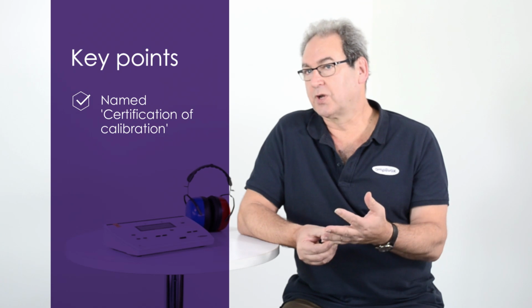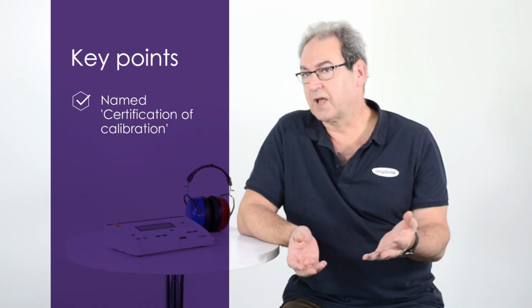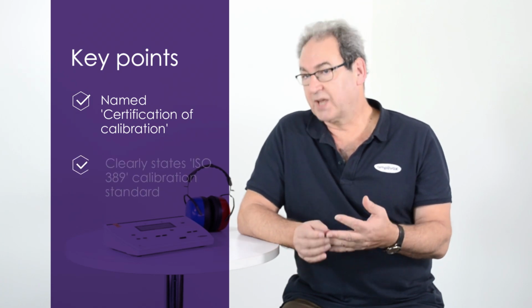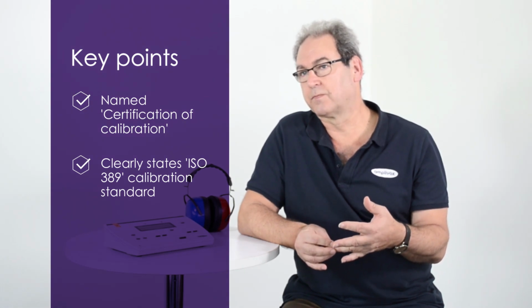So once the calibration has been completed, a calibration certificate or certificate of calibration will actually be issued for that specific audiometer and headset. The key point on a calibration certificate is the actual title says calibration certificate or certificate of calibration. Secondly, it has to identify with ISO 389.